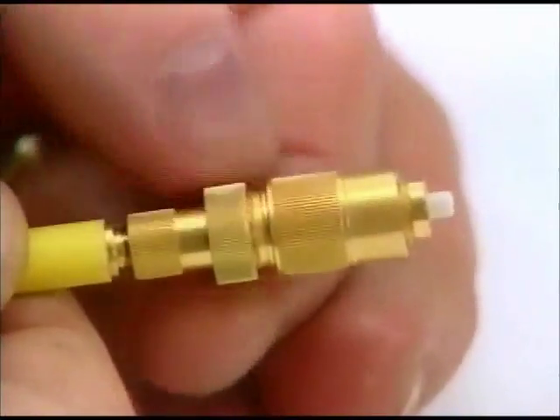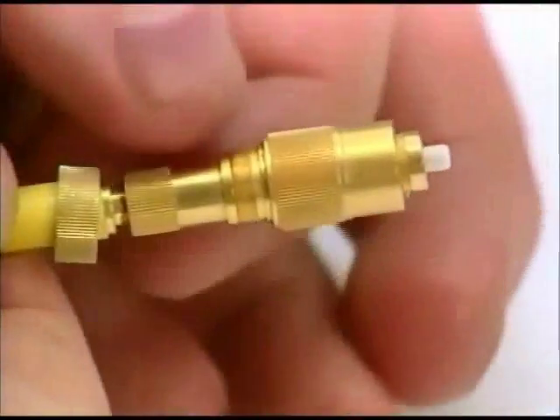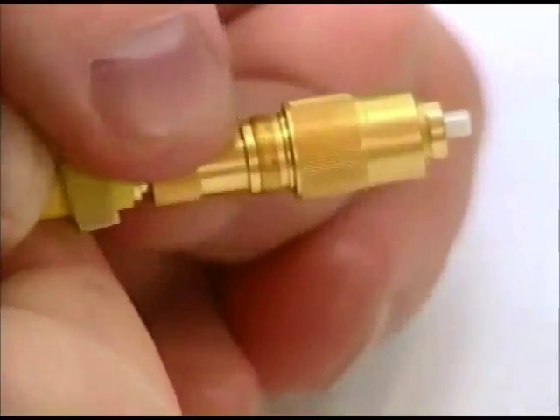So if you loosen that locking nut and bring it back by turning this section, you actually change the distance that the ferrule will stick out from the end of the connector, and that gives us our Z-axis control.